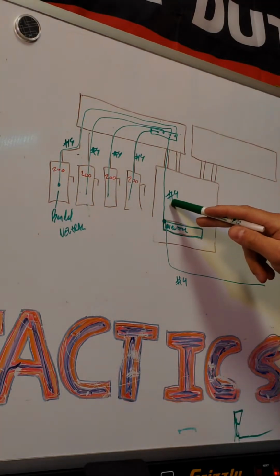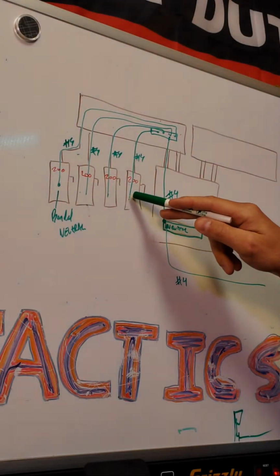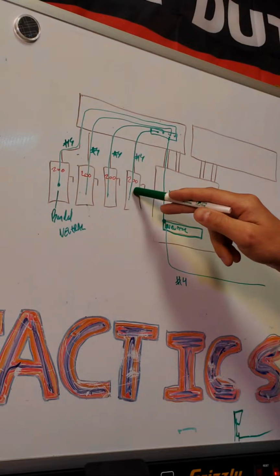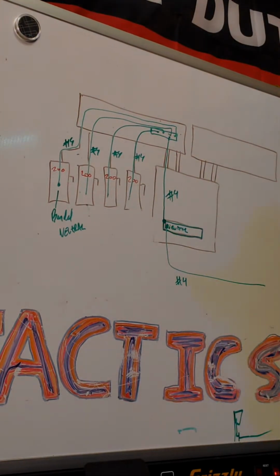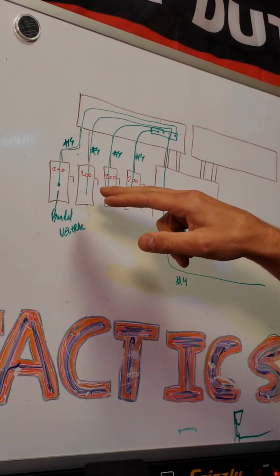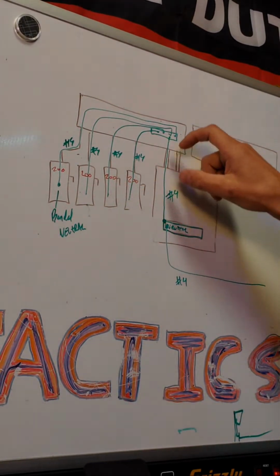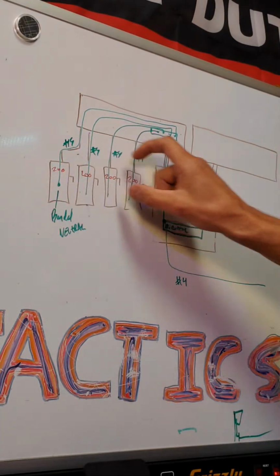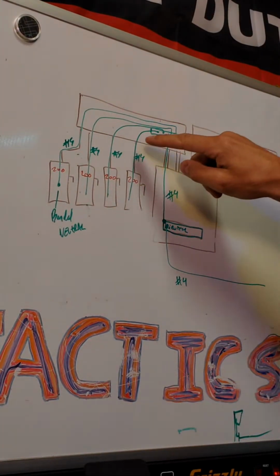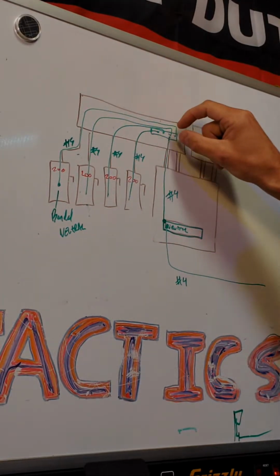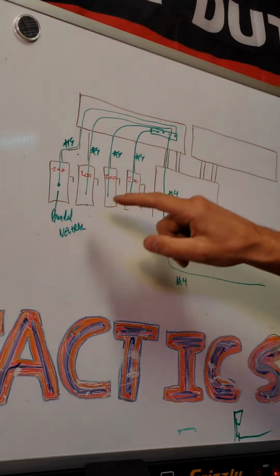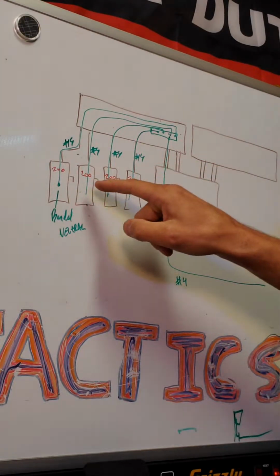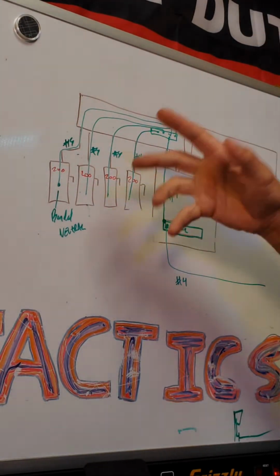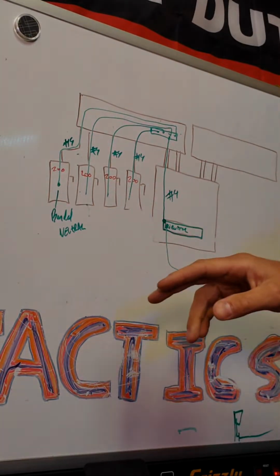Is this single number 4 sufficient to carry the burden of all 4 of those disconnects back to the source for that to be a bonded neutral? You got no overcurrent protection on this. This is all service grounds. We've got number 4 going to a common ground plate. They bonded each disconnect, which they shouldn't have done, but they did. So they created a parallel path.